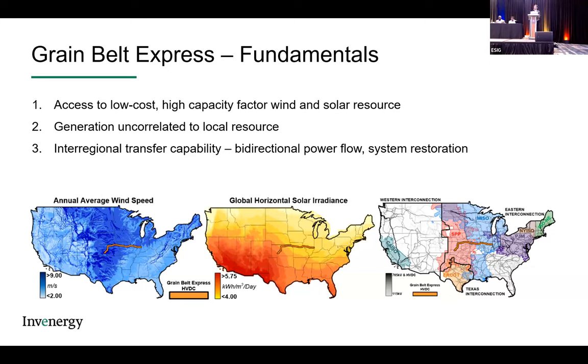And then thinking about the multi-terminal nature, you get that interregional transfer capability, bi-directional power flow. In the case of an emergency, you can send power from MISO or PJM back to SPP. You can provide system restoration benefits. I think we were talking about Black Start earlier, where the VSC could actually be used to Black Start one network from another. And you start to get into these additional ancillary services that a multi-terminal project like this can provide.